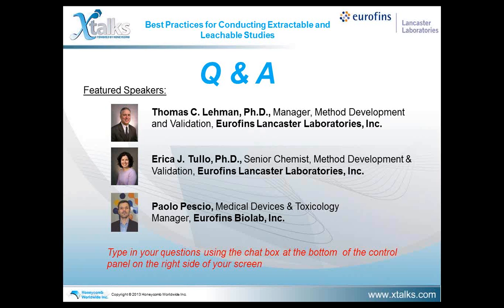Okay, another great question. When we don't have any tox data available, what we can do is perform a prediction using in silico methods. We can rank the compound using, for example, Cramer classes, starting from class 1 that poses no concern and up to class 3. So we can use in silico methods, and we can use both Cramer rules, Cramer TTC decision tree, or other tools. And generally speaking, those compounds will be followed in the next leachable study.